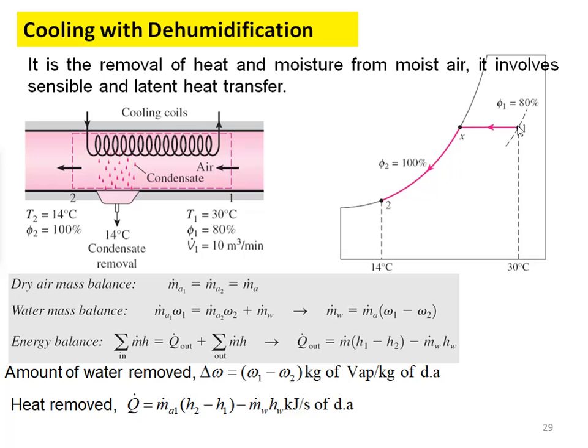On the psychrometric chart, state point one shows air entering the coil with an initial relative humidity of 80%. Initially, sensible cooling happens from state point one to an intermediate state point. Then as air passes further through the cooling coil, condensation takes place — temperature decreases along with dehumidification, reaching state point two.